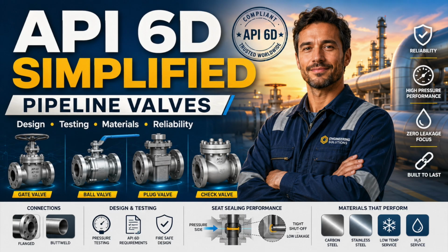You need lubricants that remain usable. You need actuator performance at the actual temperature. And you need to consider abnormal cooling during depressurization. The lowest temperature may not occur during normal operation. It may occur during the exact emergency when the valve must work.